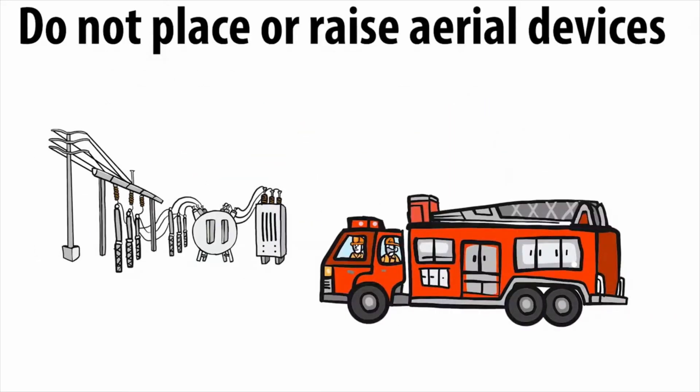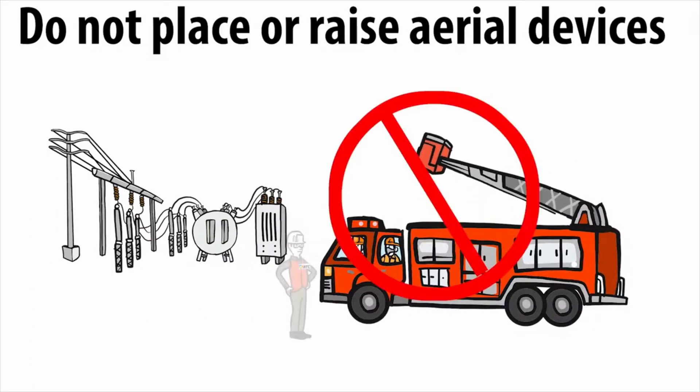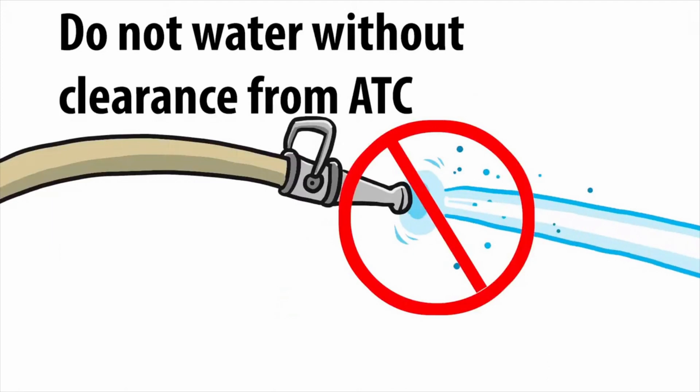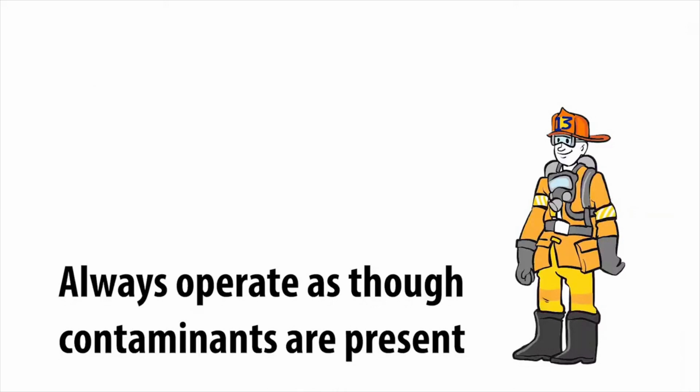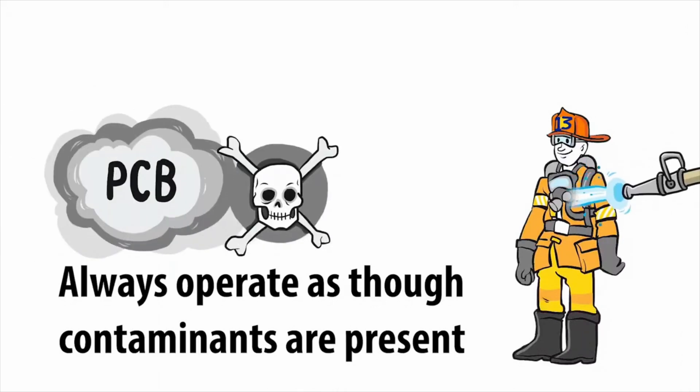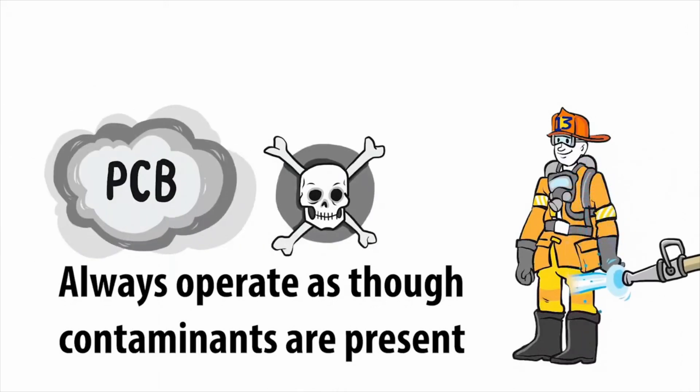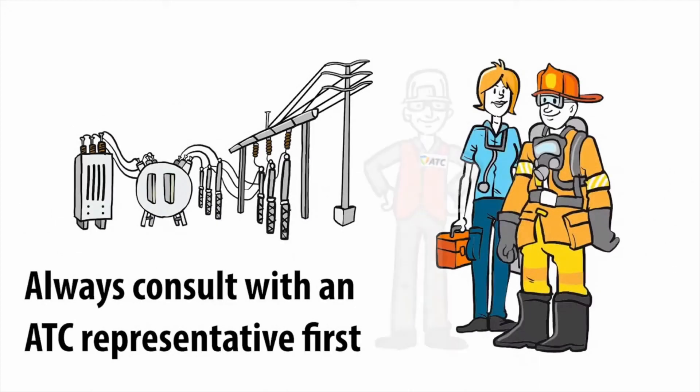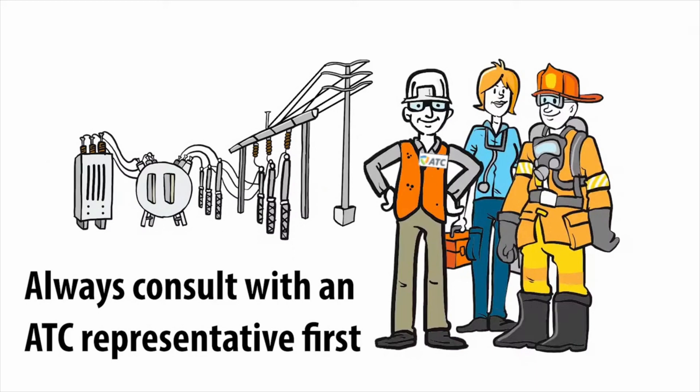Do not place ladders or aerial devices until cleared by an ATC representative. Do not use water near electrical equipment until cleared by an ATC representative. Always operate as though PCBs and other contaminants are in smoke, oil, and water runoff and decontaminate. And always consult with an ATC representative first about hazards and the safety of any tactics.